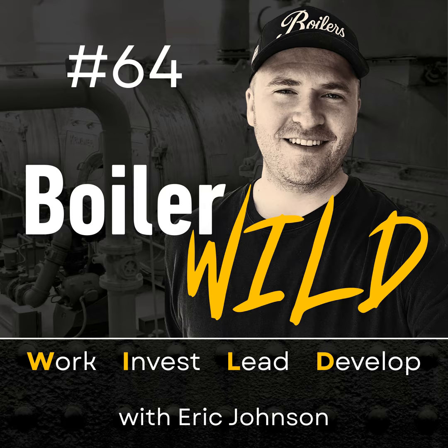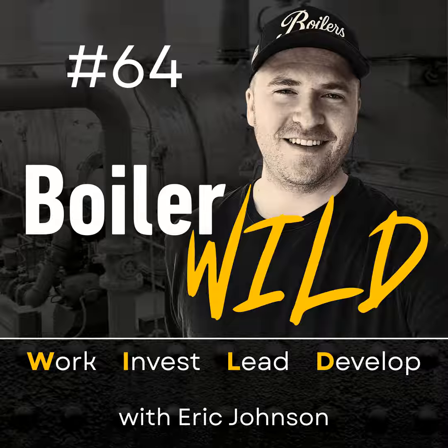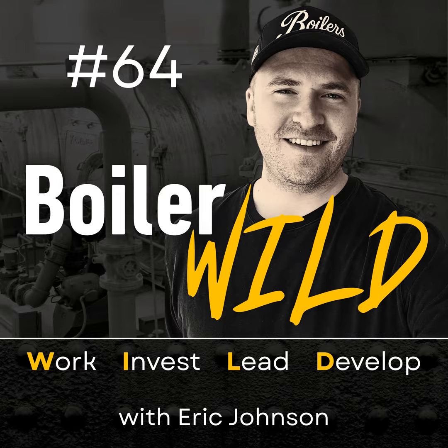So I go out there, walk into the mechanical room, and it's an older boiler. I think there was one light on the front. It was probably burned out. Their school maintenance team had been looking at the boiler for hours, and I open up the cabinet and I look at the burner control, which was a Honeywell 7800, and I don't think it had a display. So I just looked at the green power light. The light wasn't on, so I knew I didn't have power.